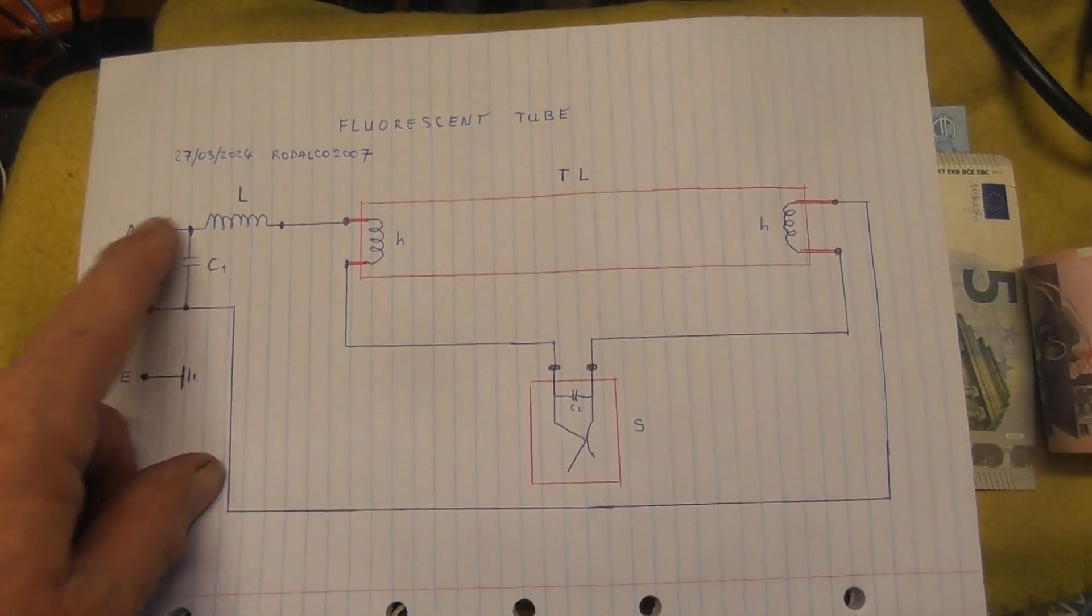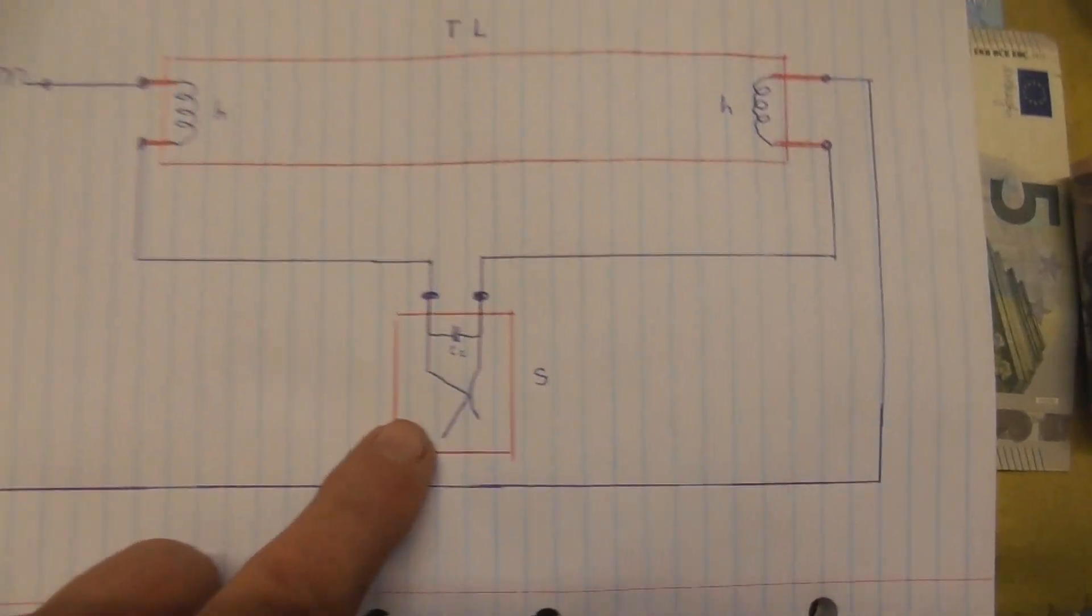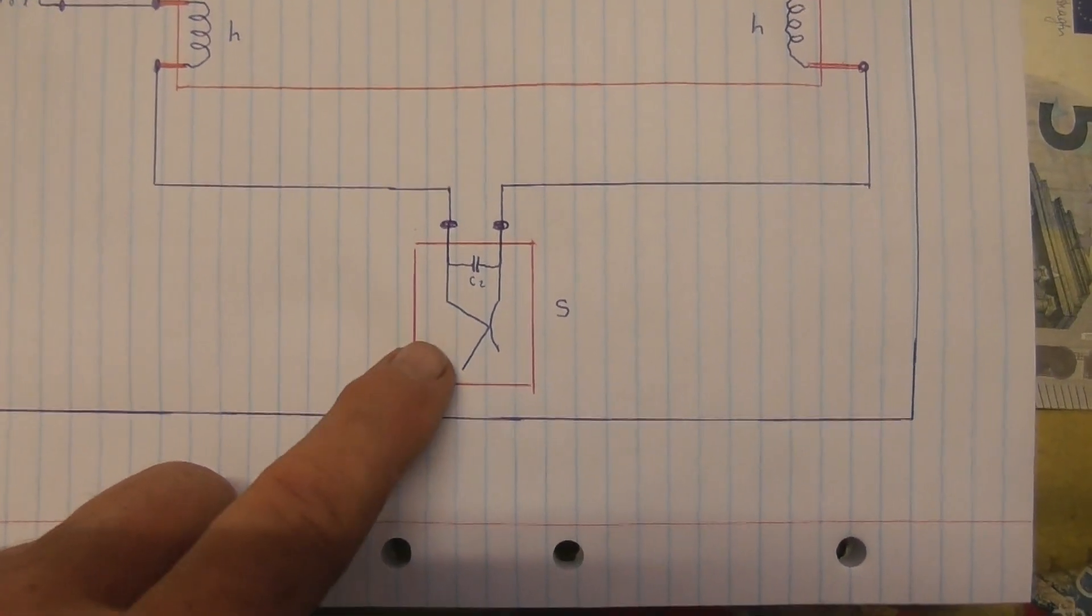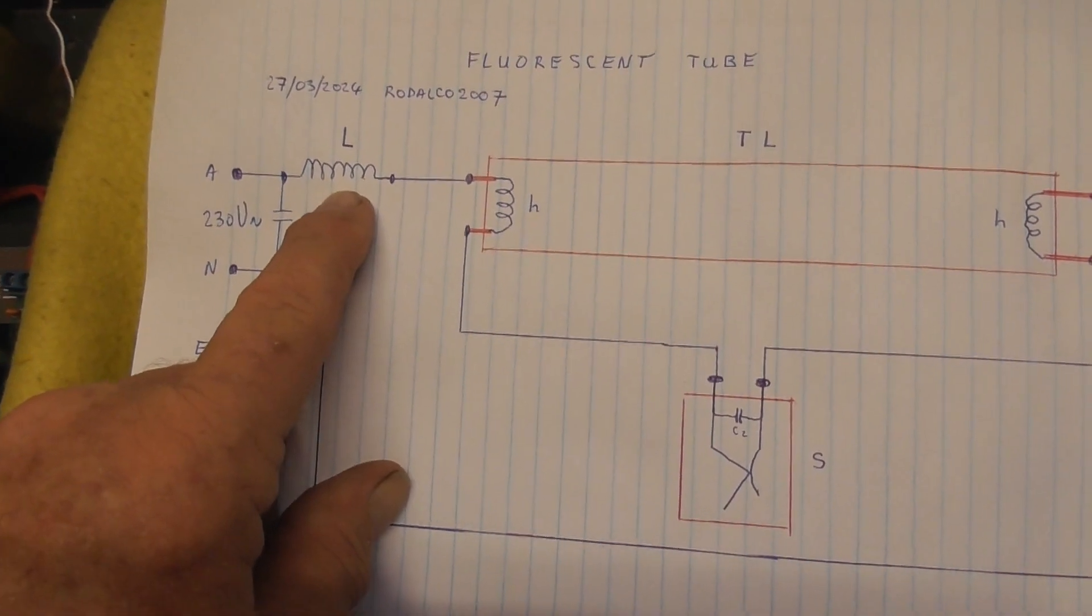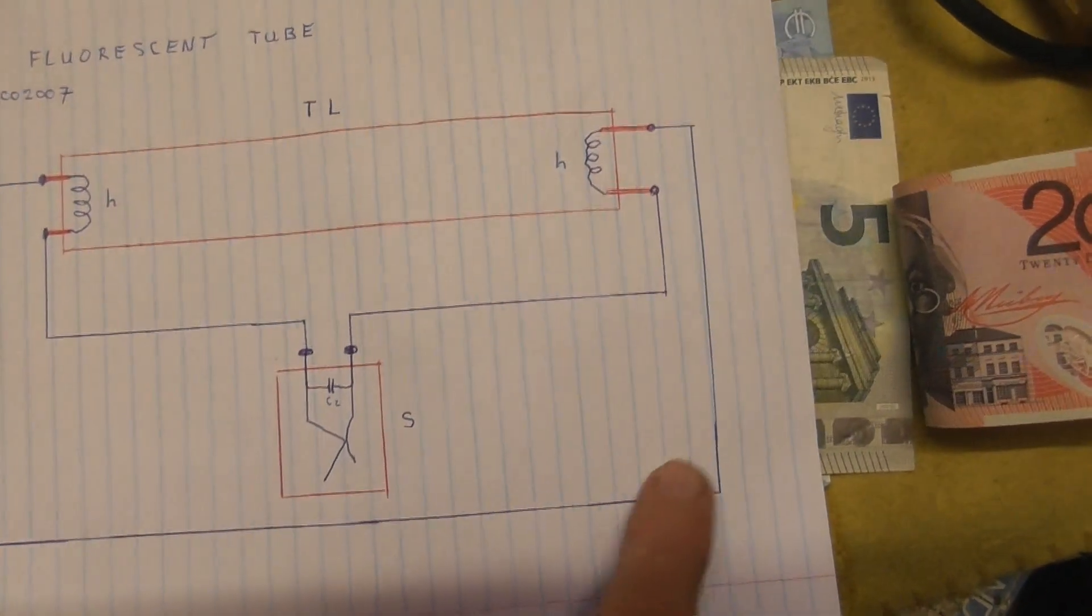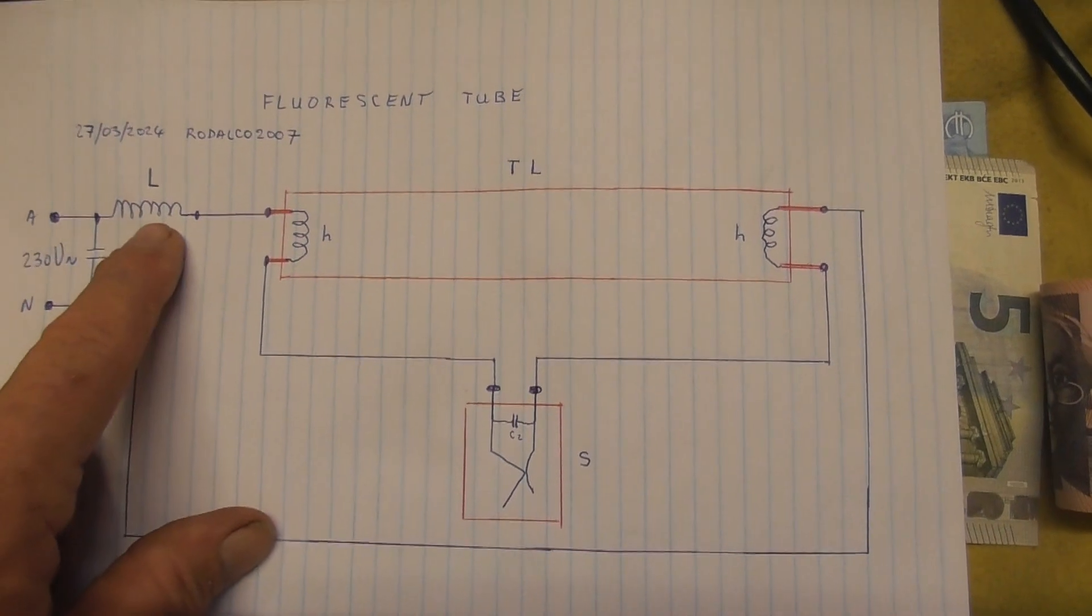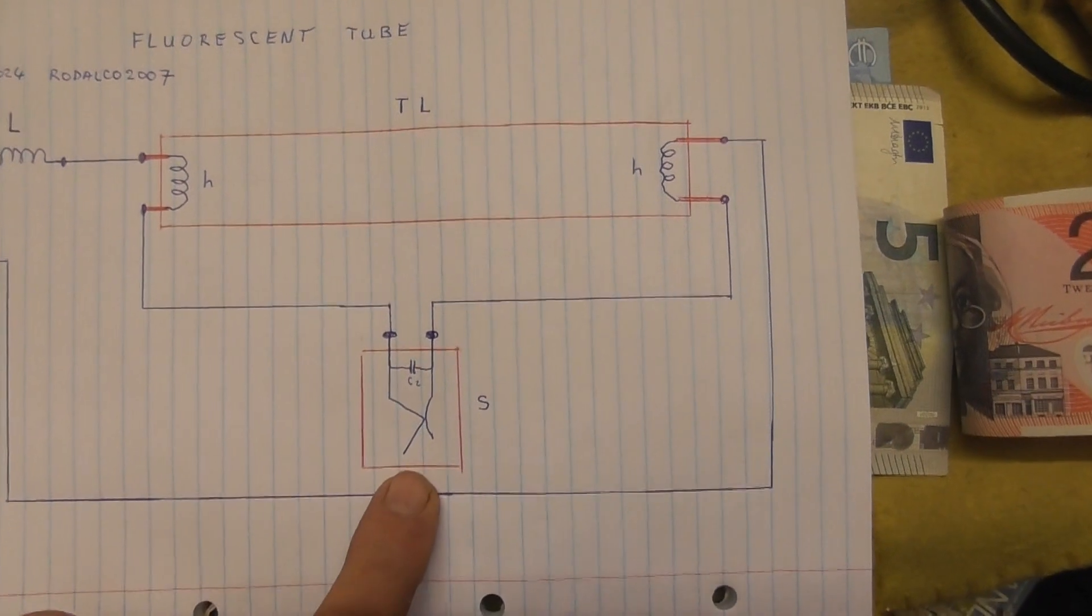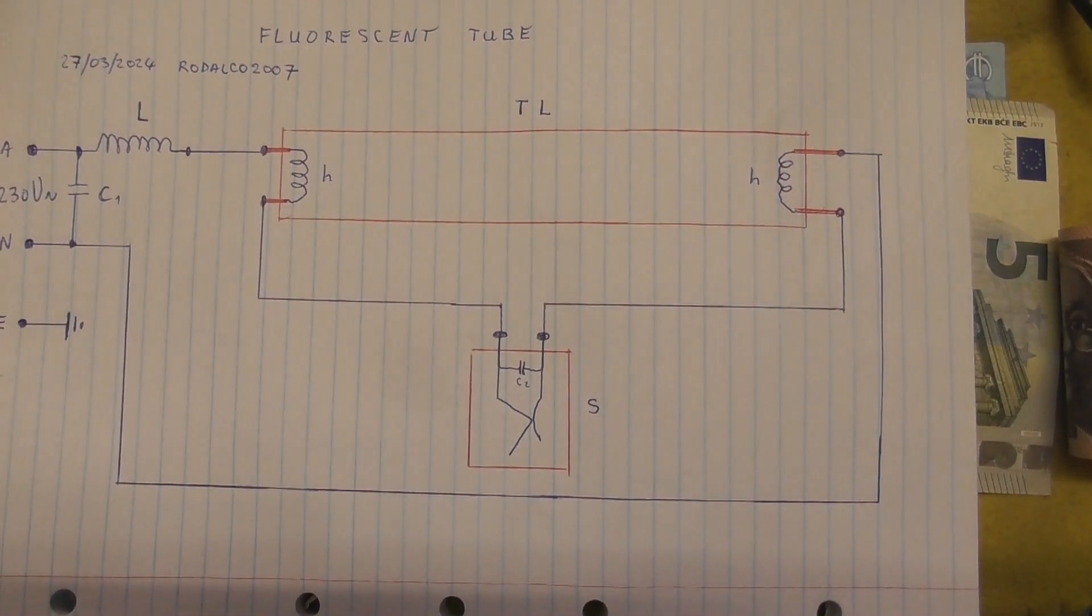Power goes in from the active. Filament one, through the starter. It's usually got a small capacitor in, and then a bimetallic strip. That opens, closes, gives a few pulses. Spike induction in the coil. And then comes to the other heater here. So they heat up briefly. Goes back to the neutral. The induction in the choke, or ballast itself, gives a high voltage spike. Lamp strikes. The starter goes open. And that's the way the lamp works. Pretty straightforward.